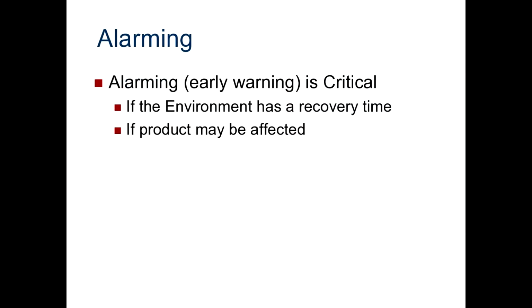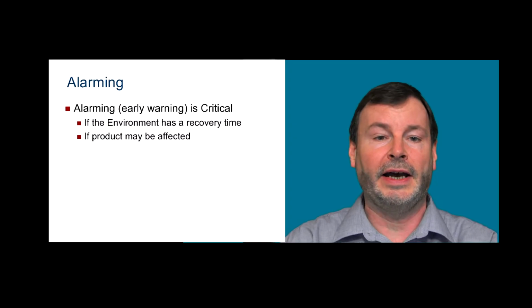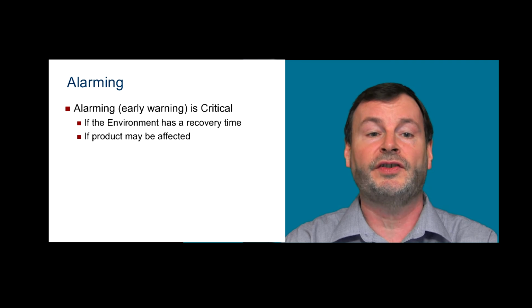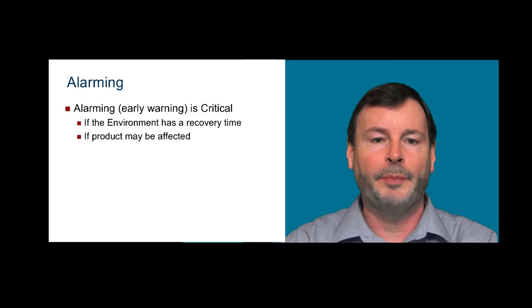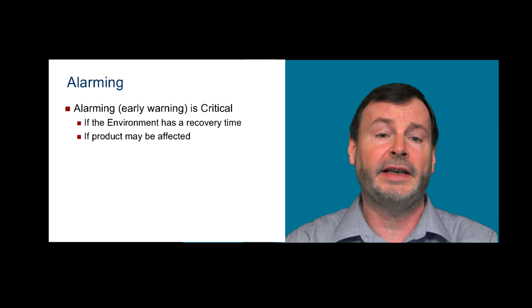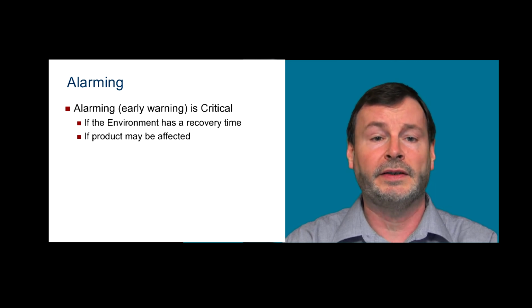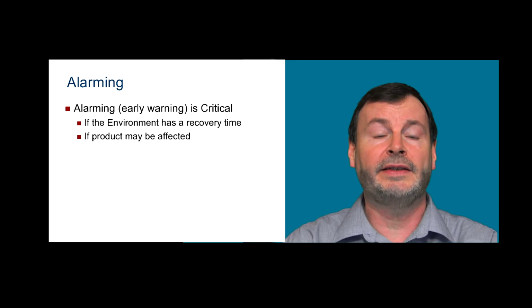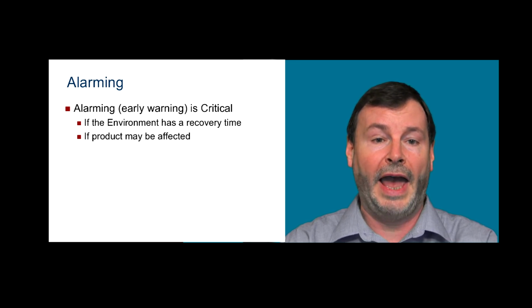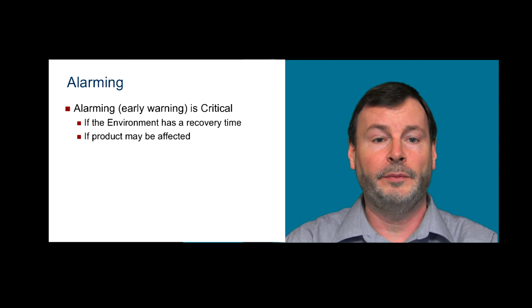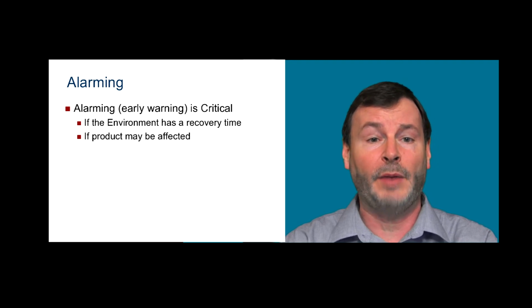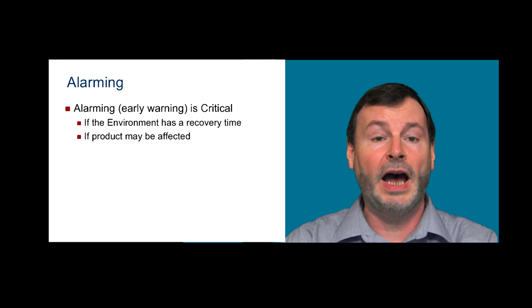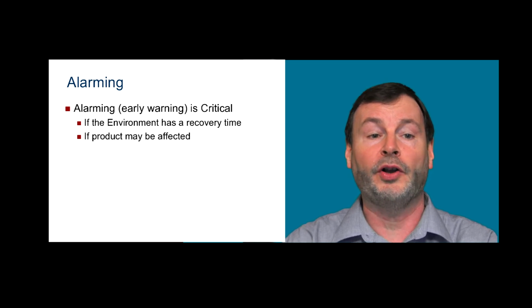Alarming can be an early warning of something that's critical, and if an environment has a recovery time, some early warning can be very valuable. By recovery time, I mean a room where if the humidity gets too low, for example, you have to stop production and rehumidify. This can happen in various manufacturing processes. Now in this case, yes, one needs an alarm to occur when you're at or below the critical level, but having an alarm system that provides early warning, maybe a few % above, can give you time to respond before you have that critical event.